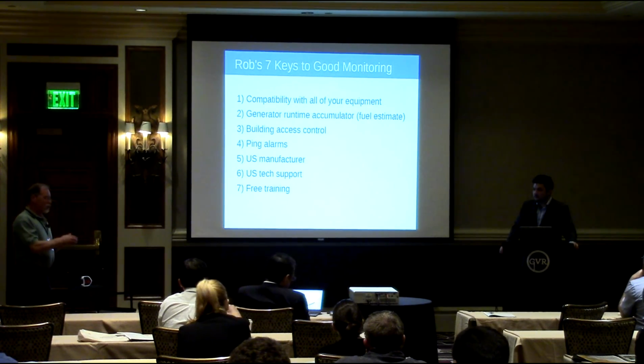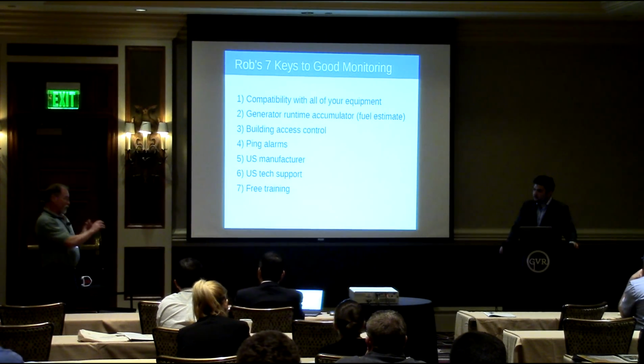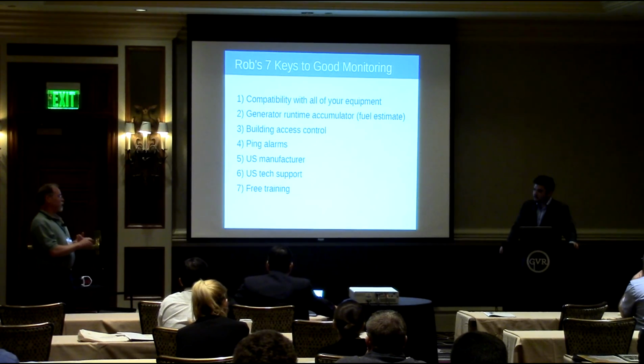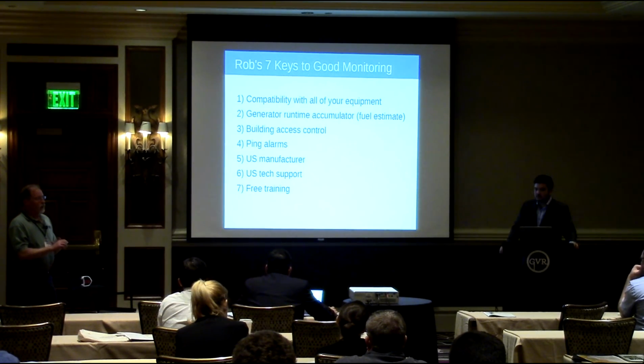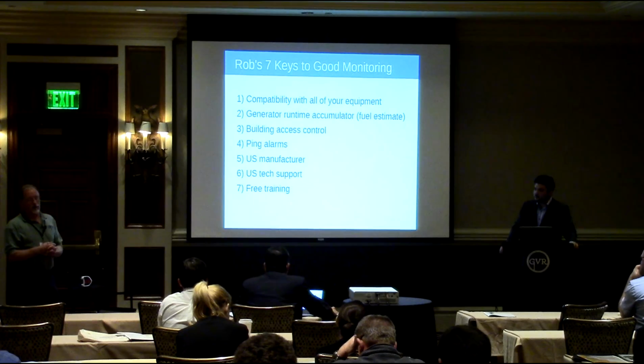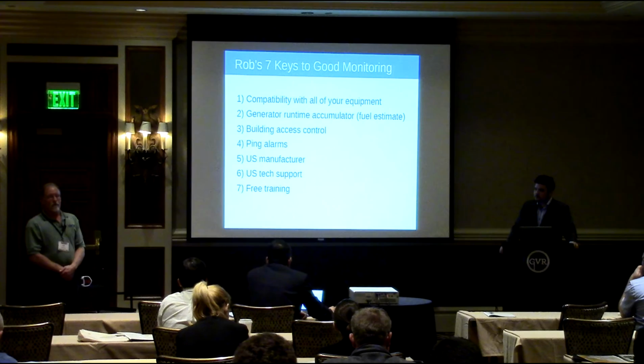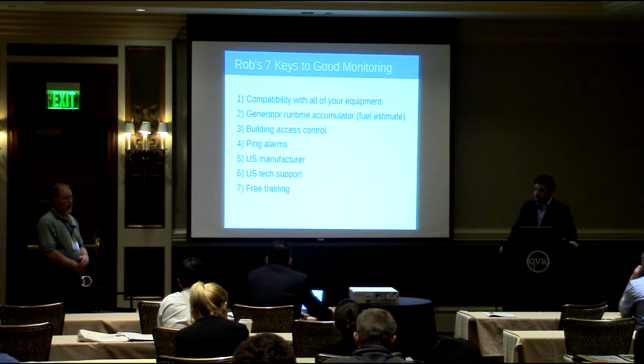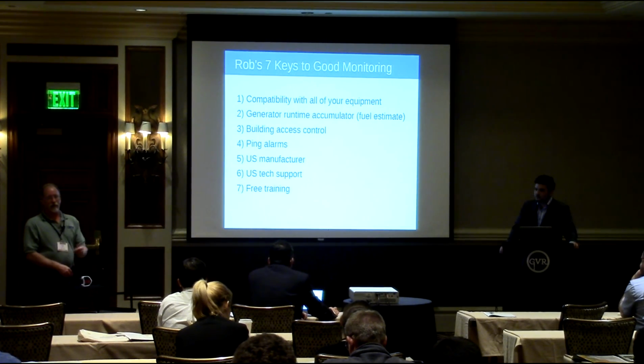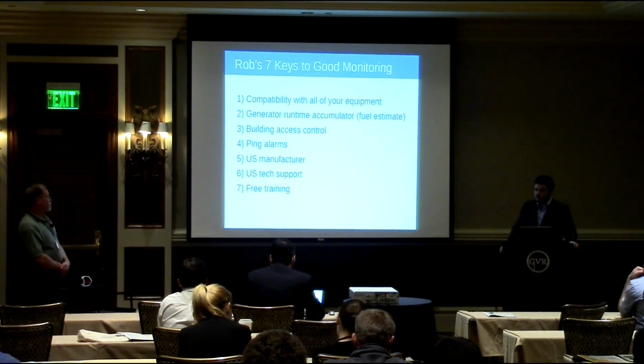And we also need to know, and what we don't do is what we're in the process of doing with DPS, we're going to be putting in fuel monitoring, how full our propane tanks are. We need to monitor that, and that's something we haven't been doing. We've been driving out to all the sites about 3 times a year and manually checking. But at a site as remote as Wolf Prairie, that generator out there may run for 2 or 3 days before they get the power up, and we might not be able to get a guy out there to monitor our propane fuel systems.